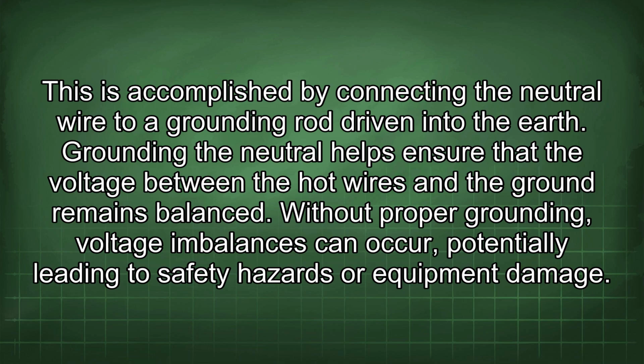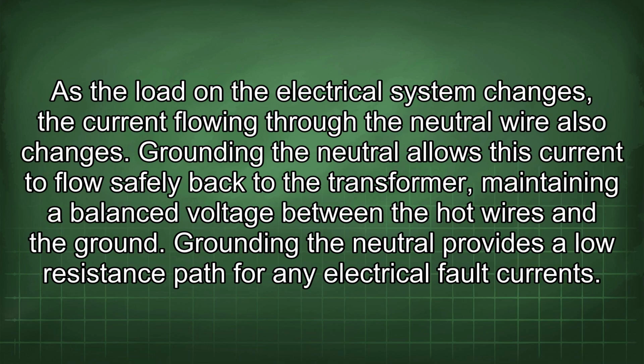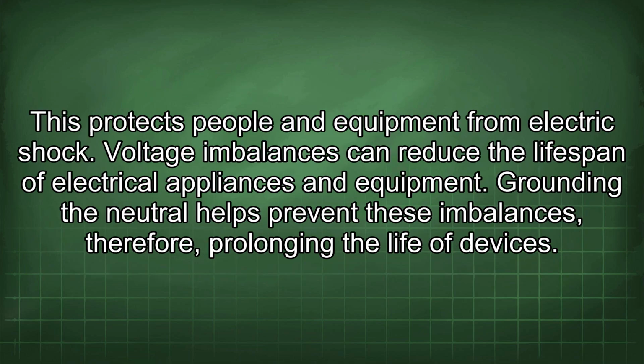Grounding the neutral helps ensure that the voltage between the hot wires and the ground remains balanced. Without proper grounding, voltage imbalances can occur, potentially leading to safety hazards or equipment damage. As the load in the electrical system changes, the current flowing through the neutral wire also changes. Grounding the neutral allows this current to flow safely back to the transformer, maintaining a balanced voltage between the hot wires and the ground. Grounding the neutral provides a low-resistance path for any electrical fault currents. This protects people and equipment from electric shock.